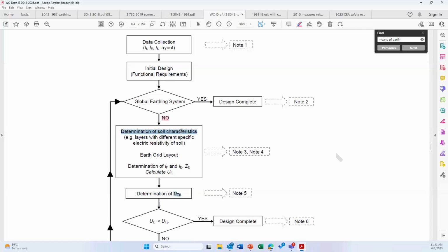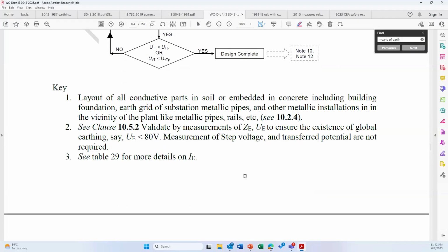Then you should do design of soil characteristics, means what is the soil resistivity, how many layers of soil are there. If you put an earth electrode, if you put an earth grid, what kind of resistances are possible. Based on the resistance, you have to find out the IF, total fault current. IE is the earth current, the partial earth fault current which is flowing through the earth electrode. Then you determine the ZE, which is the impedance of the earth electrode, and you have to calculate UE, the earth potential rise. Generally, we also say GPR, ground potential rise, which is earth potential rise. Ground is not the word which we should use in India, so we have UE, the earth potential rise. You can also take the help of note 3 and 4.